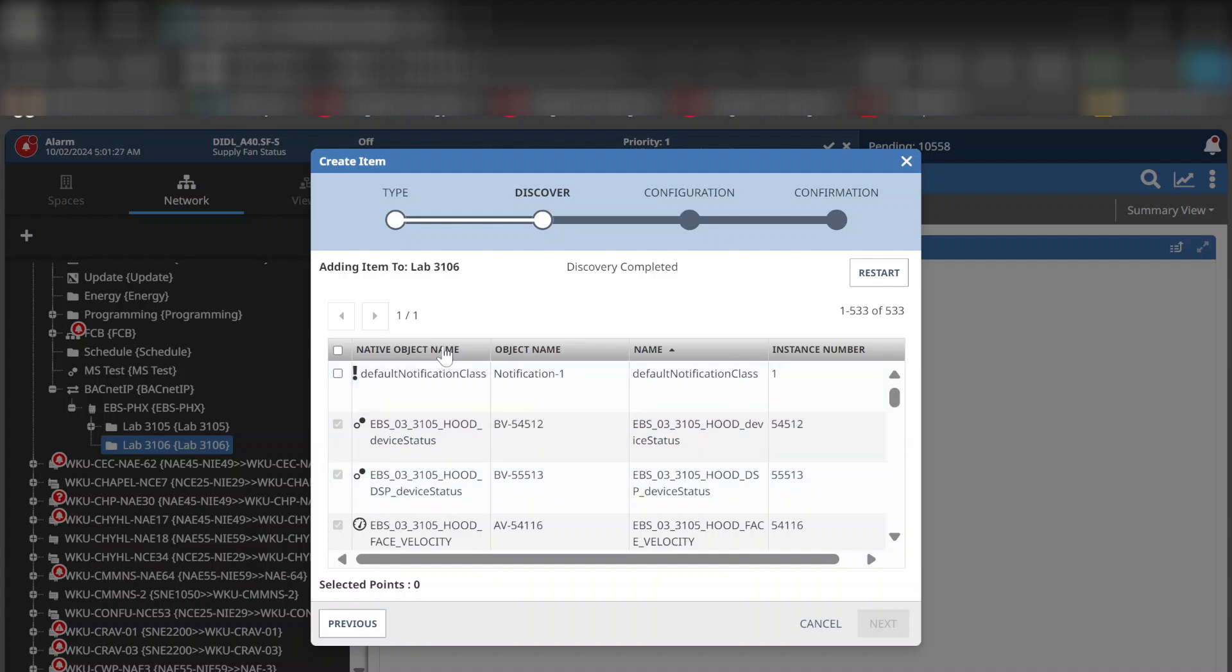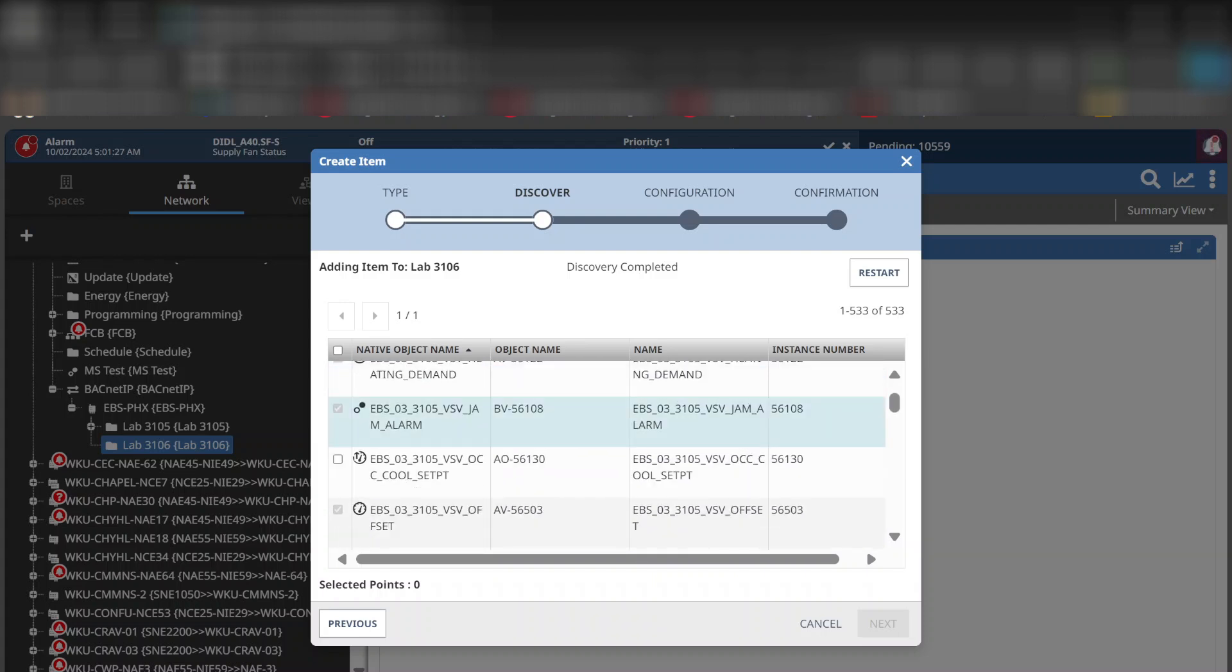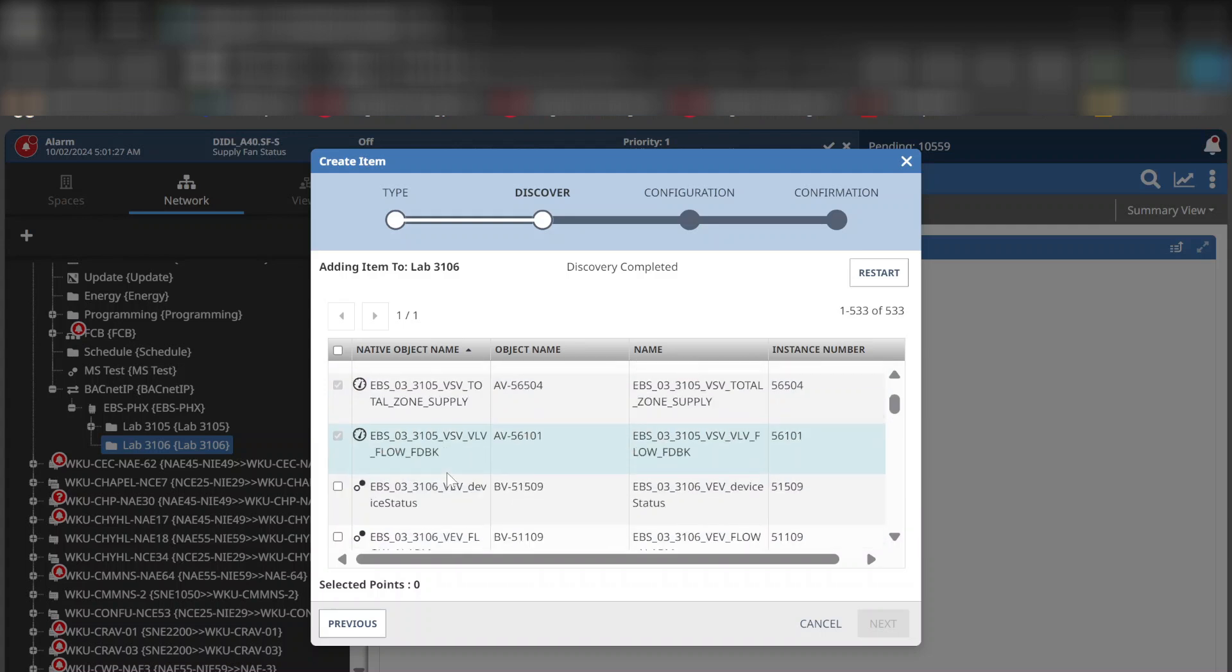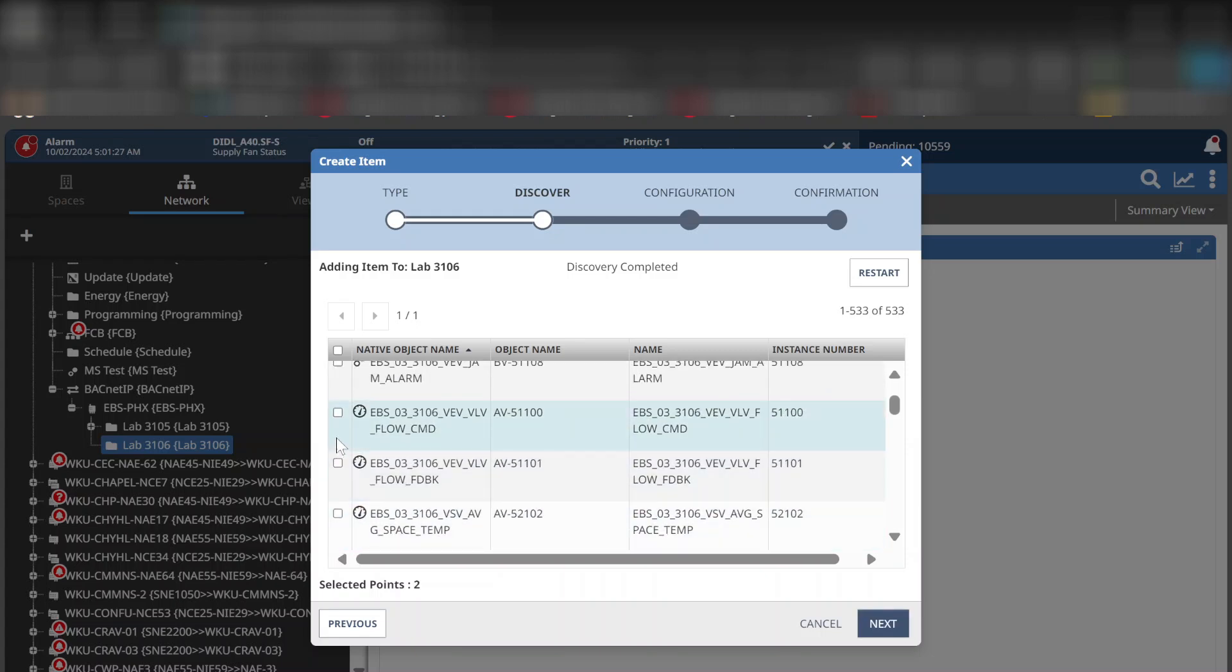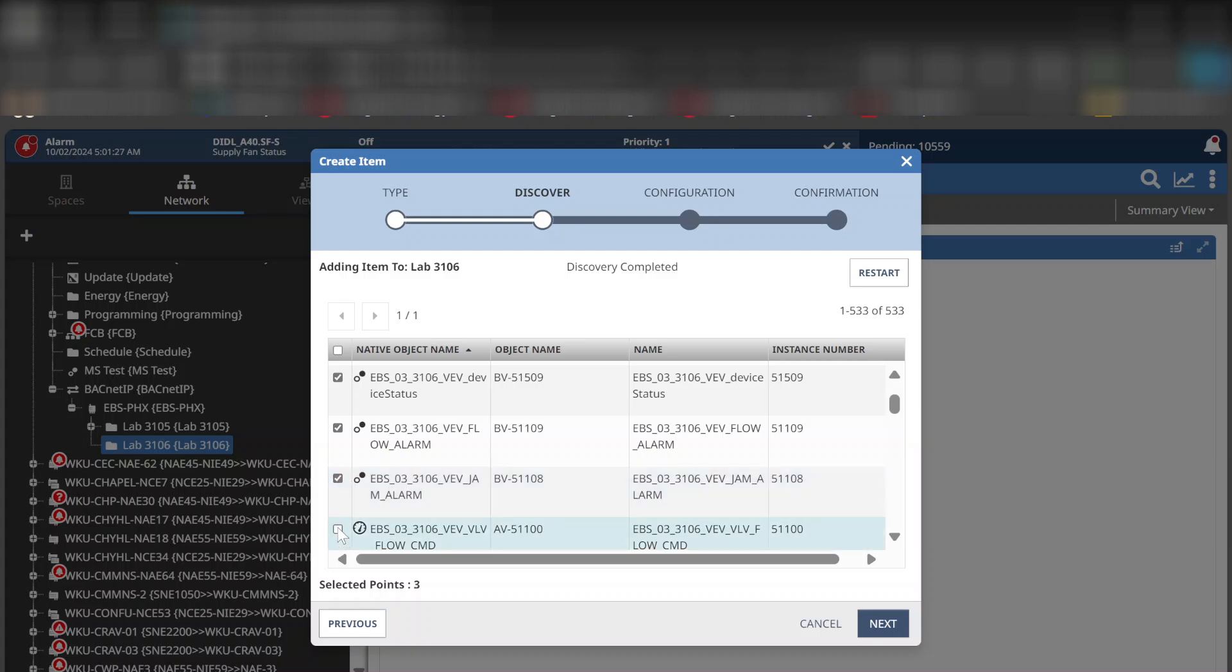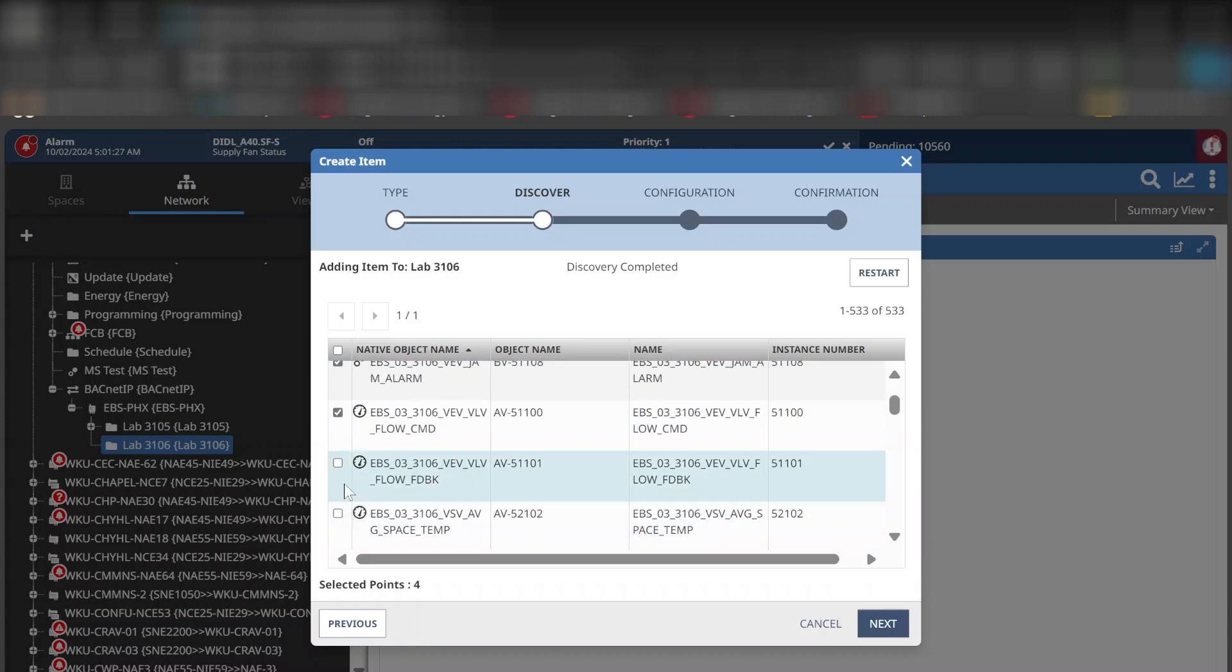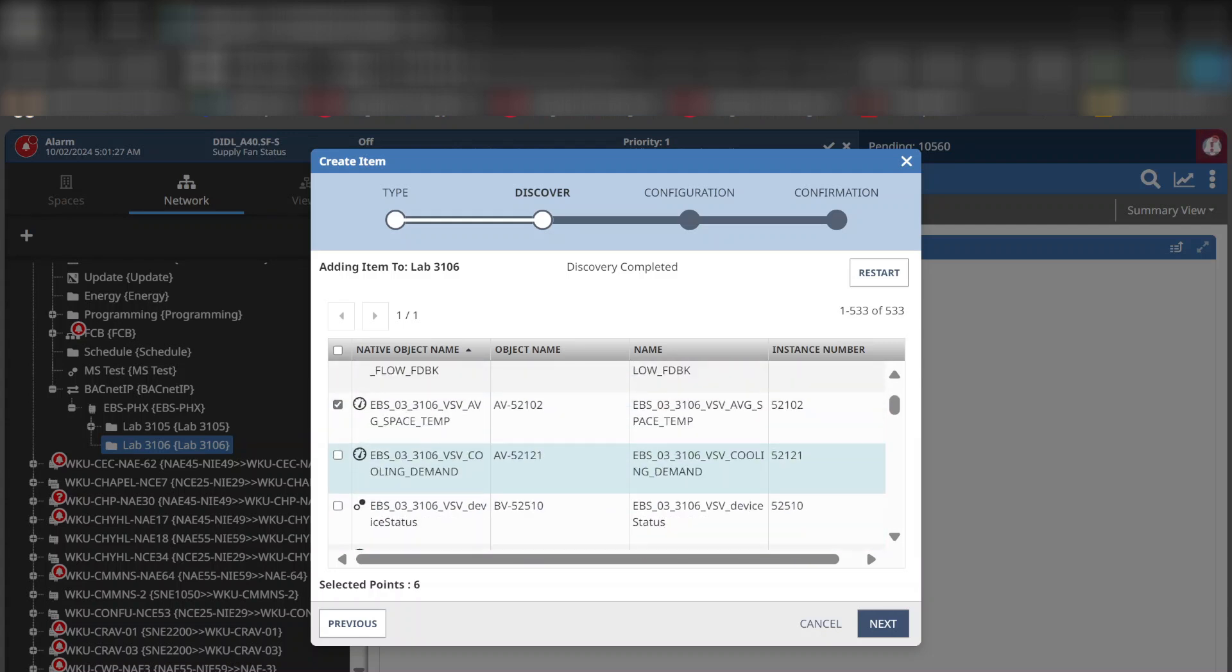Now what you have here is the ability to sort. And this is where it is much handier when we are talking about doing it in MUI. Because of the naming, the way that these are named, I'm simply going to sort them by name. And then that way it's going to group all of the room numbers for us. You can see here the points that are checked are already points that are pulled into the system. So what I need to do is simply scroll on down to where I get to where there are points that are not checked. And, of course, that is the next room in our list. And then I simply just continue checking all the way down. Just go back, double check every now and then, make sure you don't miss one. Simply scroll down, and each of these points that are related to that room, I'm simply just going to go through there and check them. Very easy that way to get those pulled into your system.